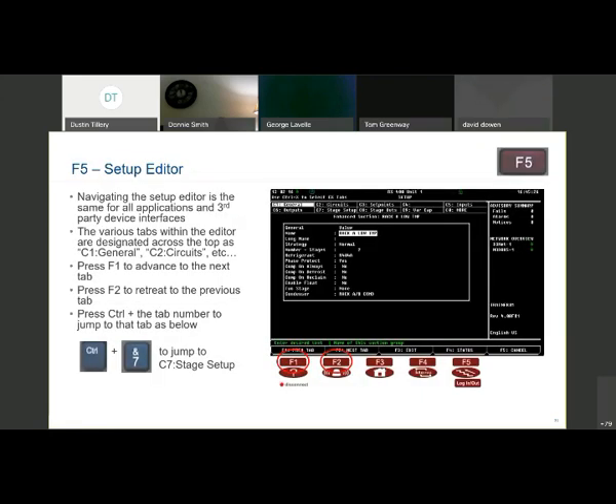To go into the setup, we push the F5 button. F5 from any status screen is going to take you into the setup of that particular application. On the setup screen, you'll see the tabs C1 through C0. These are the tabs that you're going to use for going in and programming things like your set point or your inputs, your outputs, your stage setup, what type of compressors we have. Things like that are going to be done through the setup editor.